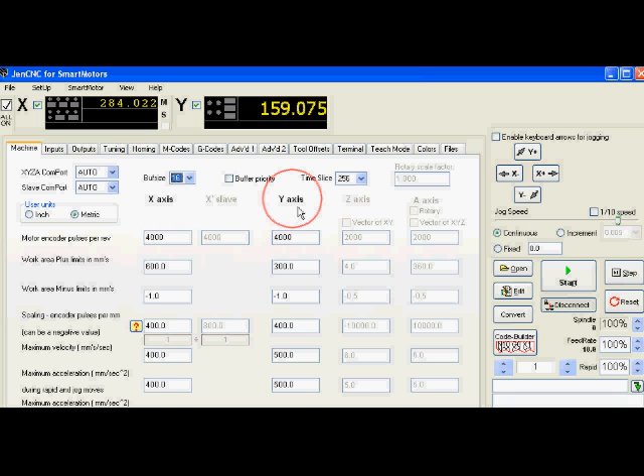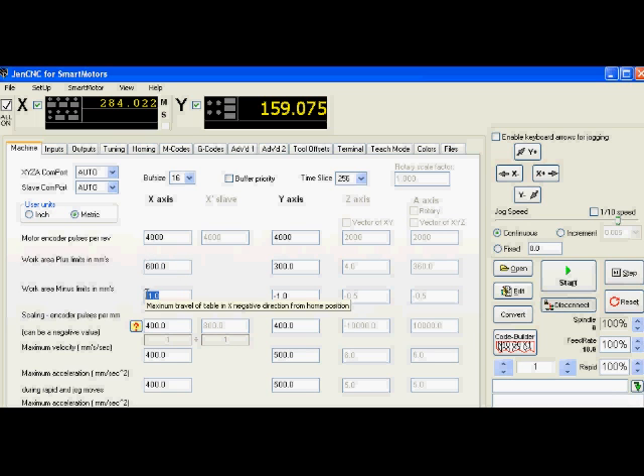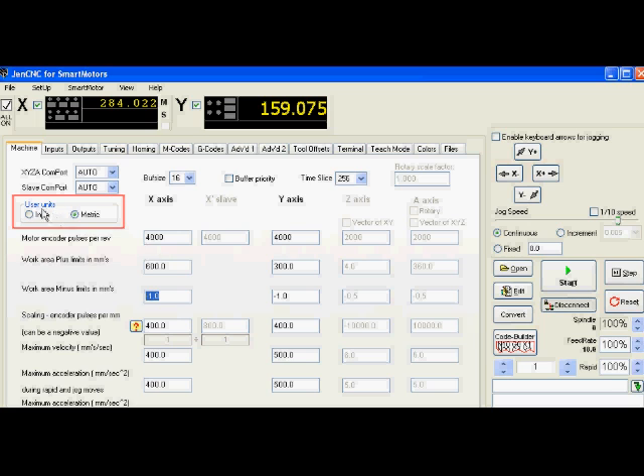My X axis has a 4000 count encoder. It's 600 millimeters of stroke. Actually there's about 625 millimeters of usable stroke. I'm going to set my minus work area to negative 1 millimeters. If you see up here the user units, you can switch to inches if you prefer instead of metric. Everything that we sell in terms of linear motion control systems is in metric, so I'm going to stick with metric.